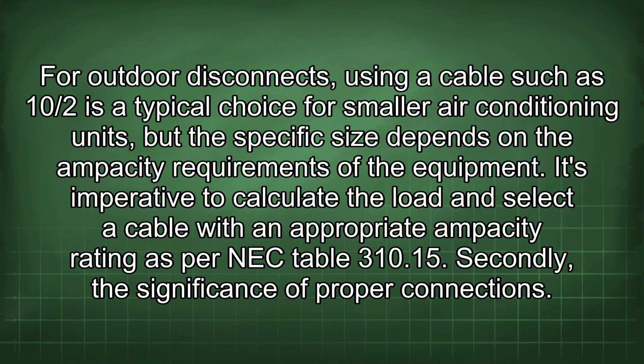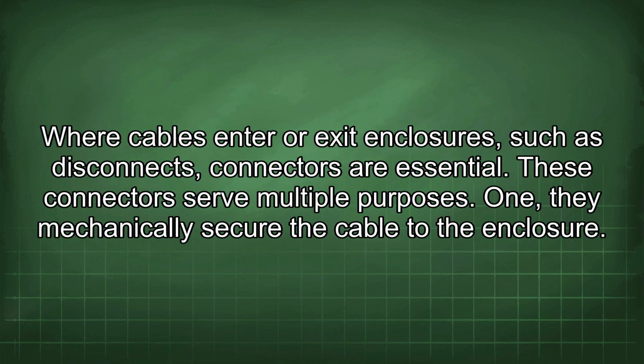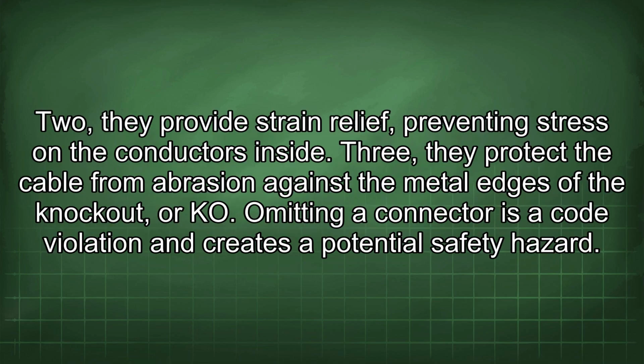Secondly, the significance of proper connections. Where cables enter or exit enclosures, such as disconnects, connectors are essential. These connectors serve multiple purposes. 1. They mechanically secure the cable to the enclosure. 2. They provide strain relief, preventing stress on the conductors inside. 3. They protect the cable from abrasion against the metal edges of the knockout, or KO. Omitting a connector is a code violation and creates a potential safety hazard.